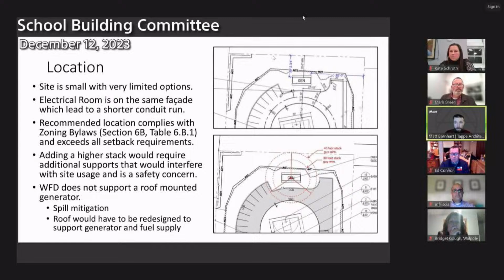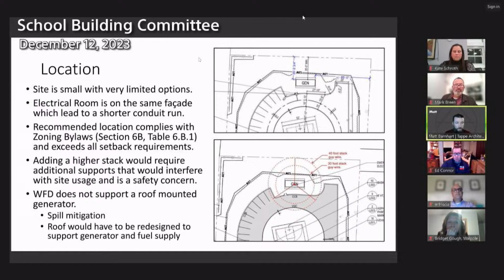We looked at adding a higher stack, but adding a higher stack requires additional supports and guy wires, which come off of that at a 45-degree angle. If you look at the diagram at the very bottom, it shows different options for the diameter of where the guy wires are. Those interfere with the usage. Some of them would interfere with the driving access lane that goes back behind the school. That's the fire department's access road to the back of the building. So the guy wires would interfere with that drive. And they also get very close and tight to the property line, depending on what stack option you go with. Also, the fire department does not support a roof-mounted generator due to spill mitigation. And the roof would also have to be redesigned to support the generator and the fuel option if we looked at that.